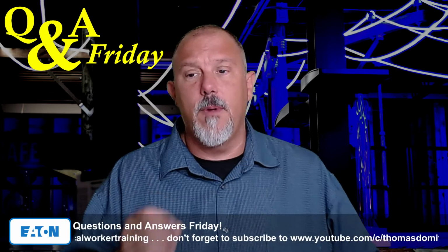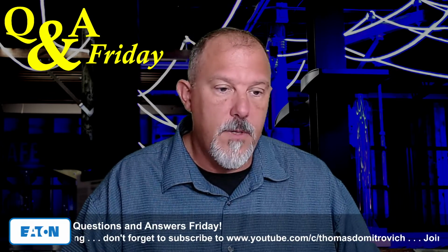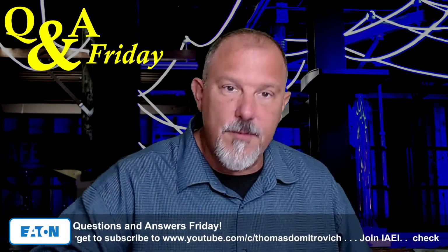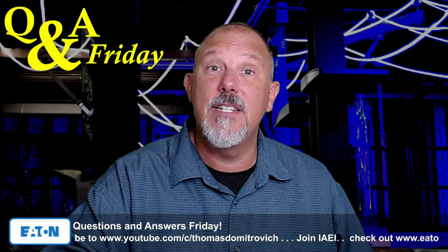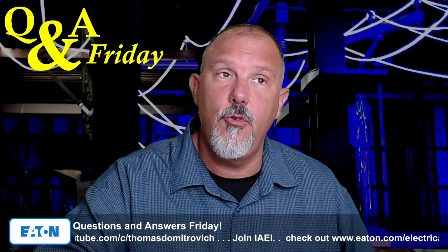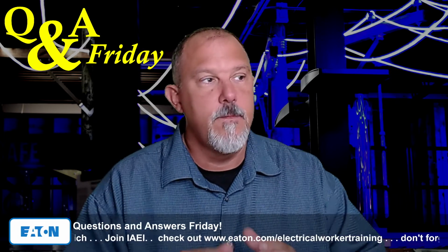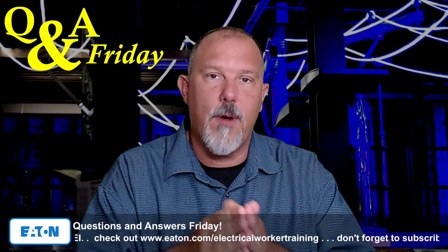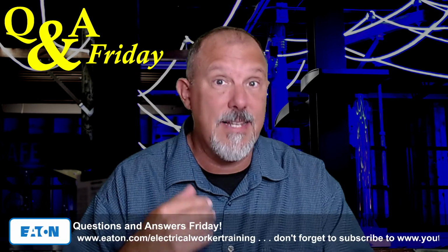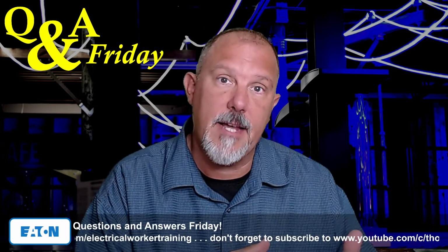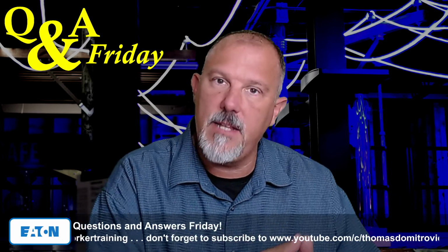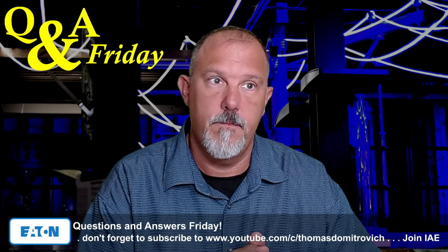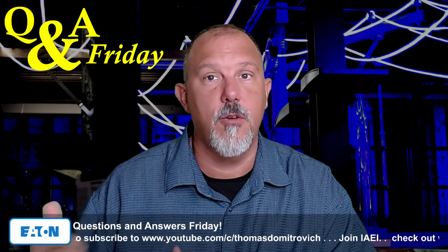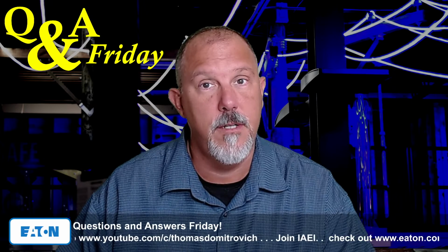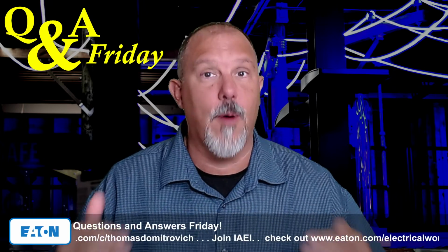The thought process here to remember is that, Matthew, simply grounding something does not mean you will not be electrocuted. Okay, and why do I say that? Grounding and bonding helps trip the overcurrent protective device, yes, for when you have short circuit type of events. But a very high impedance fault internal to that unit does not mean you're going to trip the thermomagnetic circuit breaker that's protecting that unit just because you have grounding.